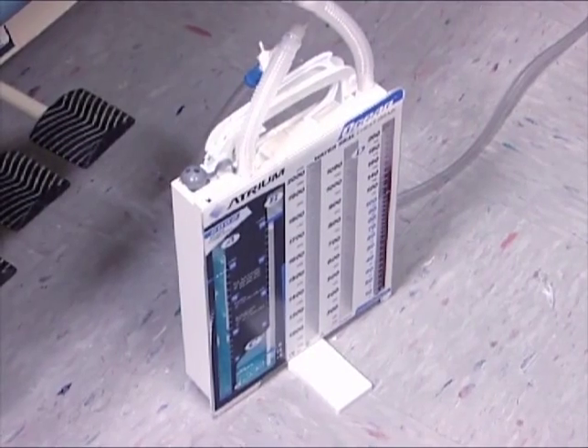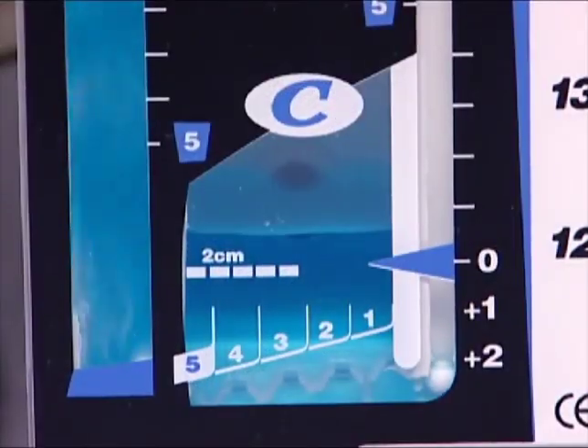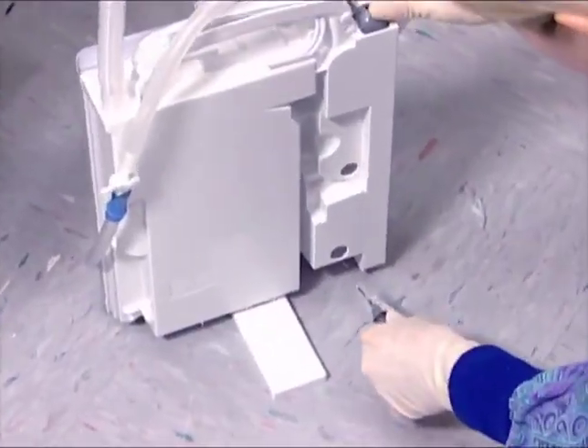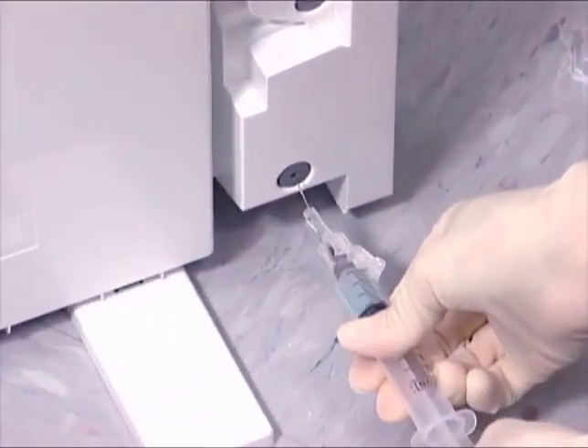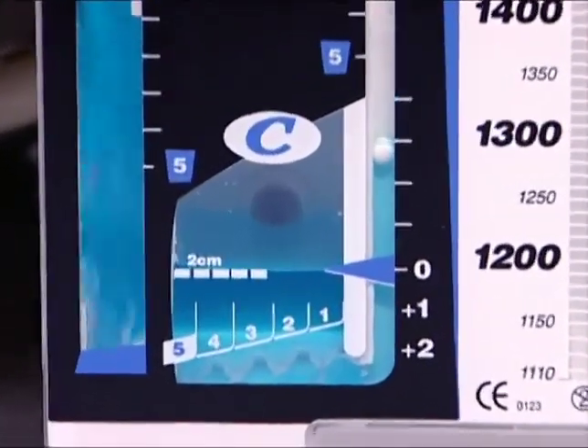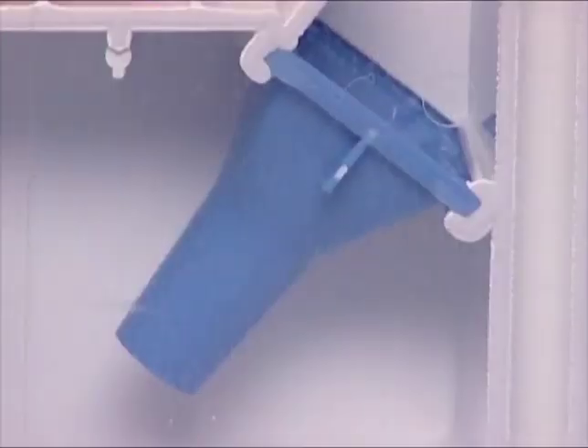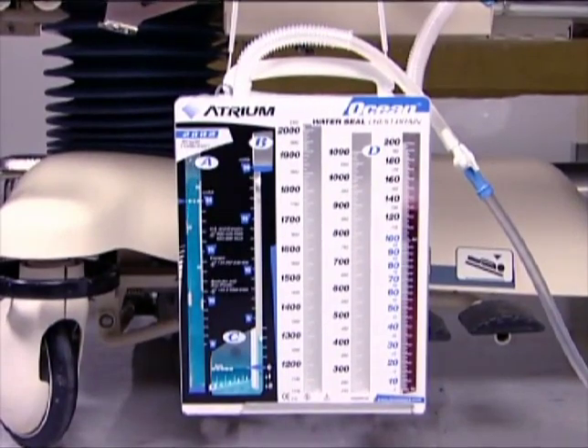When monitoring a patient's chest drainage system, it's important to periodically check the water seal's operation and fluid level. If the water seal is either underfilled or overfilled, it should be adjusted accordingly to the prescribed maximum 2 cm level. Using a 20 gauge needle with syringe, adjust the water level via the grommet located on the back of the water seal chamber. The Ocean features an advanced water seal design for maximum knockover protection, even when connected to suction. In the event of an accidental knockover, its knockover nozzles help minimize interchamber spillover for the ultimate in system reliability, user convenience and patient safety.